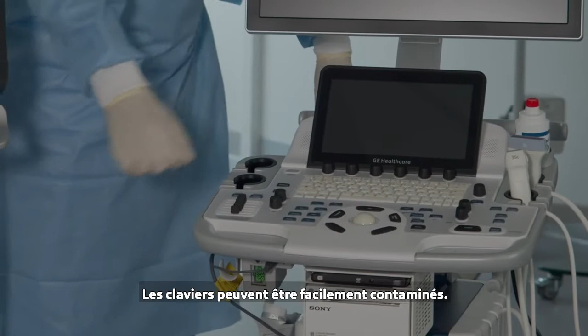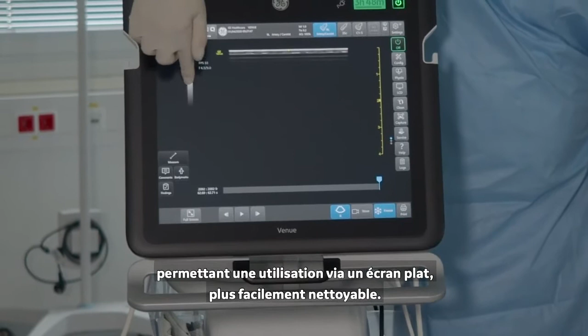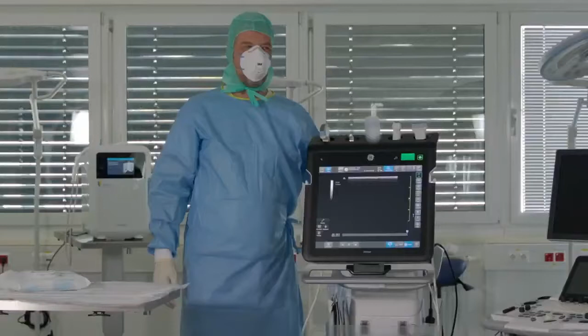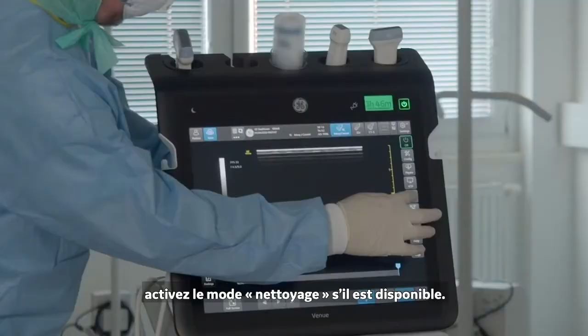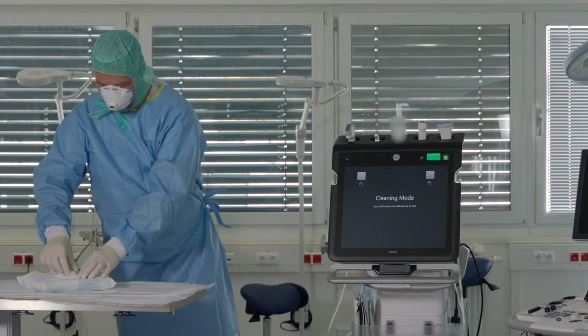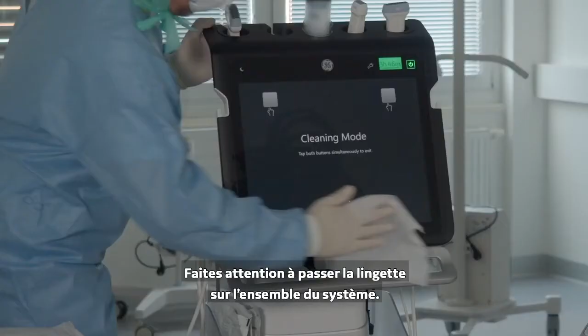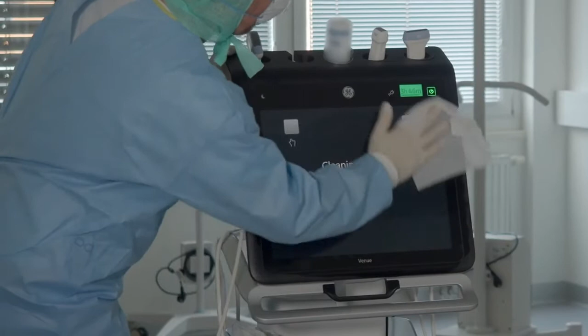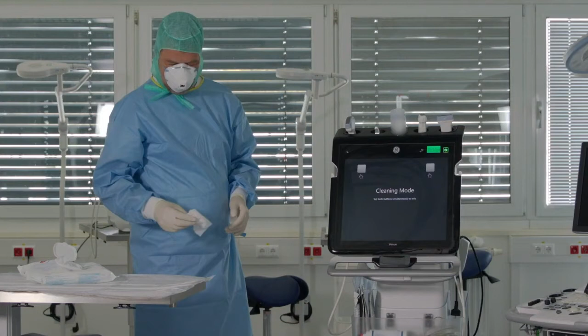Keyboards may become contaminated, so some scanners might use touchscreen displays, allowing operation of the scanner from a flat panel that is easily disinfected. Prior to cleaning these touchscreen displays, you may want to put the system in cleaning mode if it's available. Then, wipe the screen and its surroundings gently. Be sure to use a systematic approach and wipe the entire system. Leave the display to dry and only then turn the screen back on.